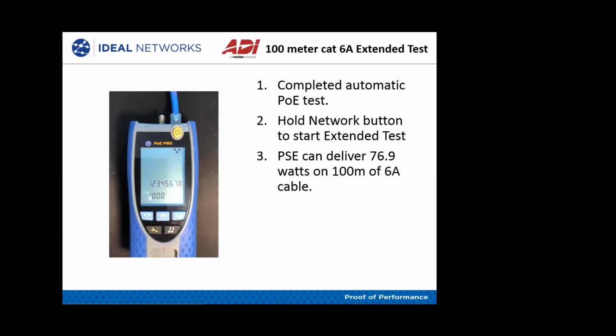This is critically important when dealing with long runs of cable. In the electrical world, the longer the run, the more voltage drop you're going to have. So this basically allows you to test all of the infrastructure, the cabling, whether it will support the wattage, as well as the power sourcing equipment.